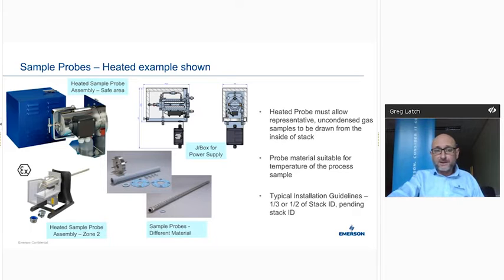Some of these materials of construction, as we suggested, if you've got, for example, HF acid as carryover, HCl, etc., potential emissions, or even heavy loading particulates, you do have to very much look at the best wetted, or if you like, call it exposed materials of construction. And then that follows through to things like blowback, for example. We've got blowback scenarios, and more importantly, definitely from a CEMS point of view, you've got calibration re-entry point. So you actually re-enter your calibration gas at the point of takeoff. And the methodology for that is you're proving and testing the full function of the measurement system. So there's no shortcuts there from a CEMS aspect. For process control, it can differ slightly.